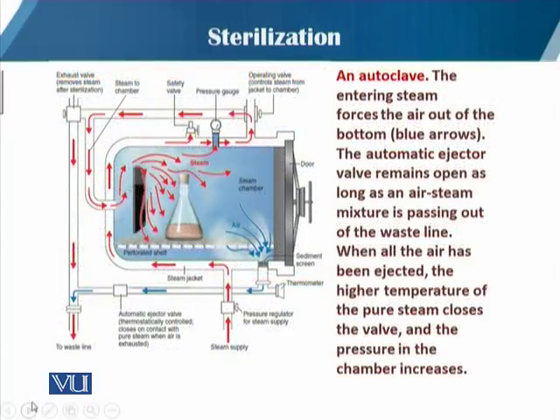So here you can see that mostly in batch sterilization, the autoclave is used for sterilization purposes. So what is the function of the autoclave? It maintains a pressure of mostly 15 pounds just to maintain the temperature of 121 degrees Celsius. You can see in this slide by the red lines how the steam enters the autoclave chamber, and when the steam is entering the autoclave chamber, the air oozes out. When all the air has oozed out, the whole container is filled with steam, because wet heat is required in the autoclave process. If the air remains as a pocket, then that space cannot be fully sterilized.